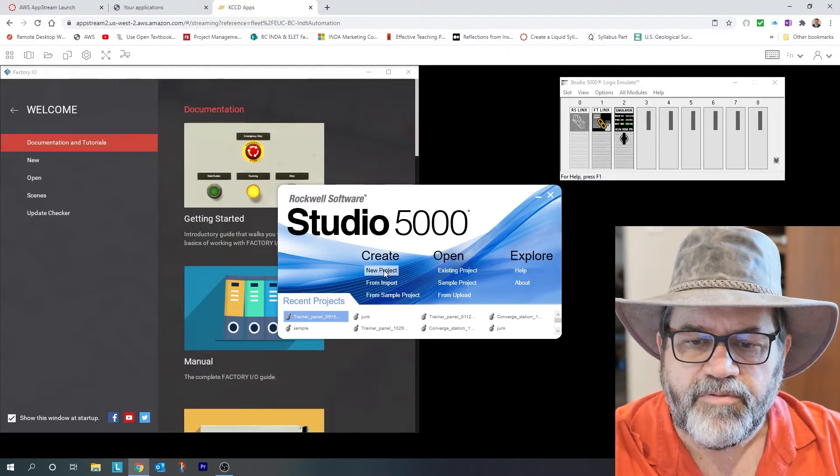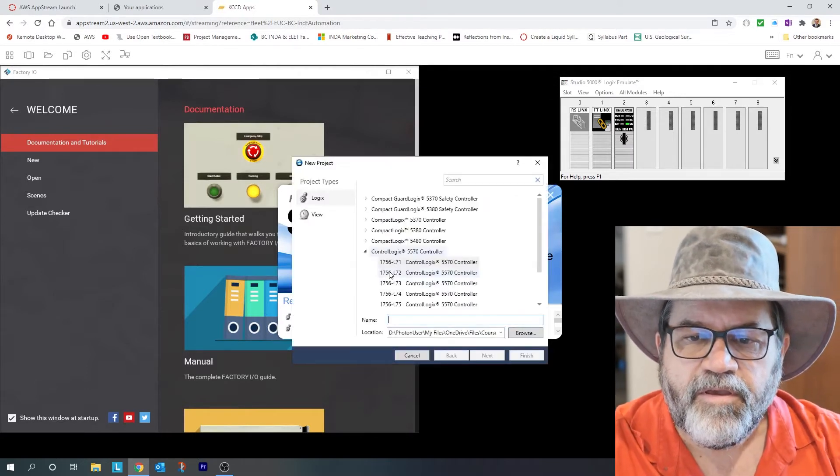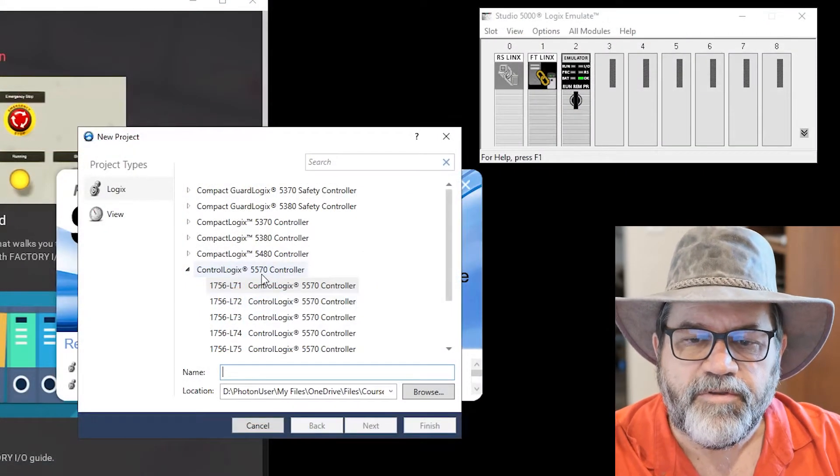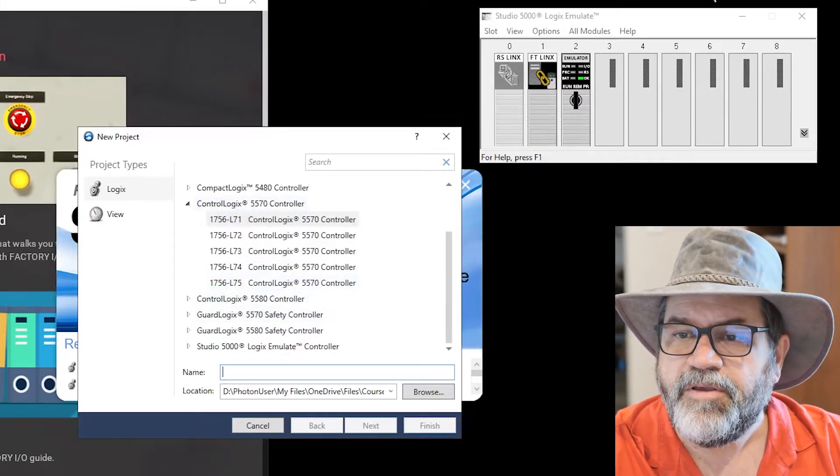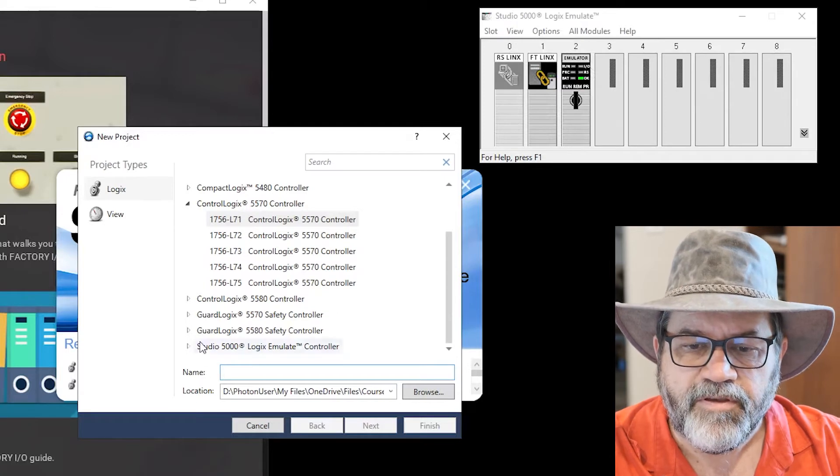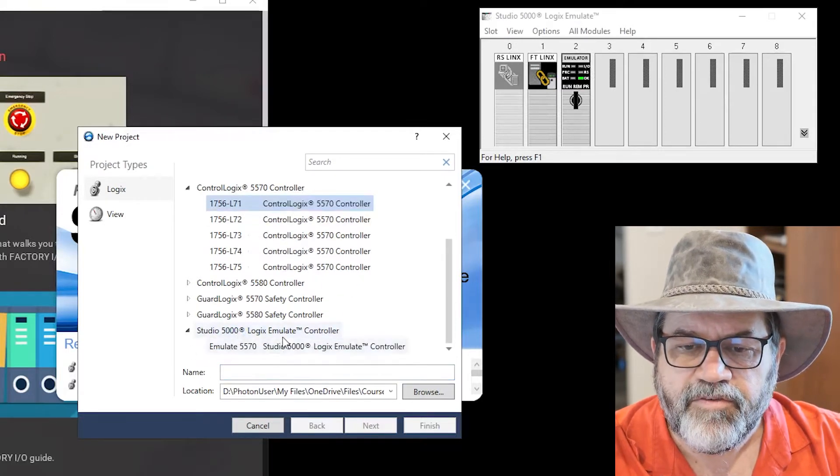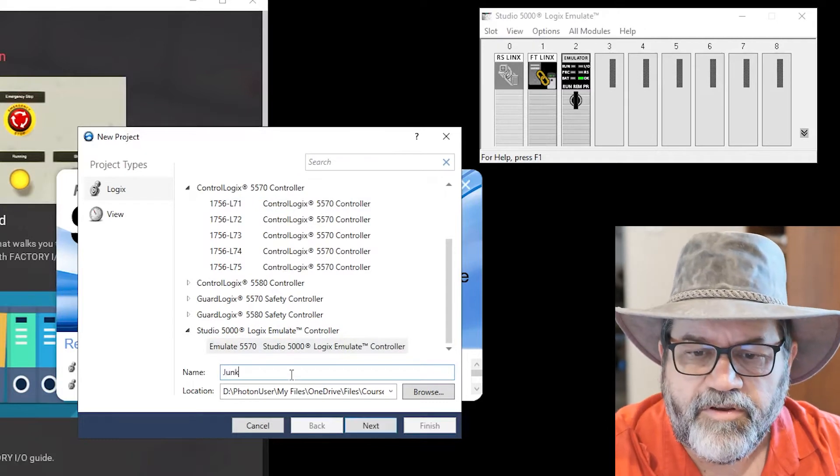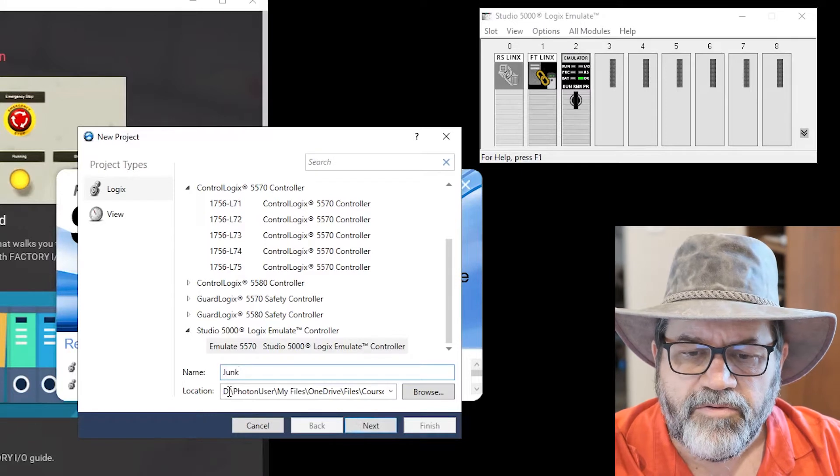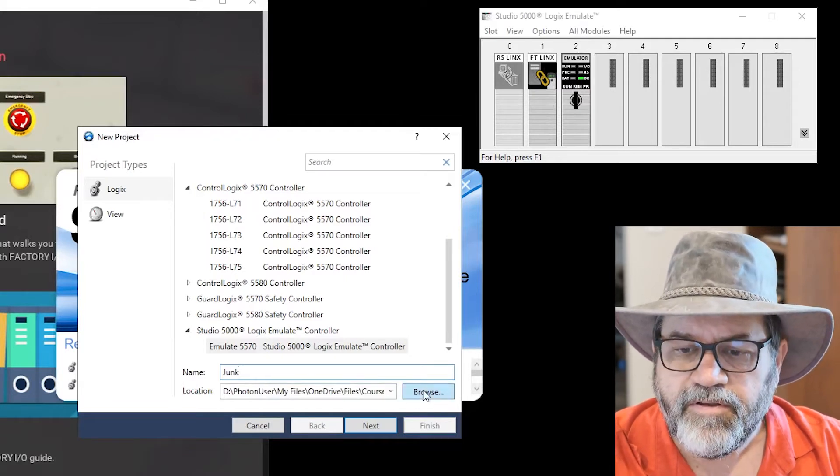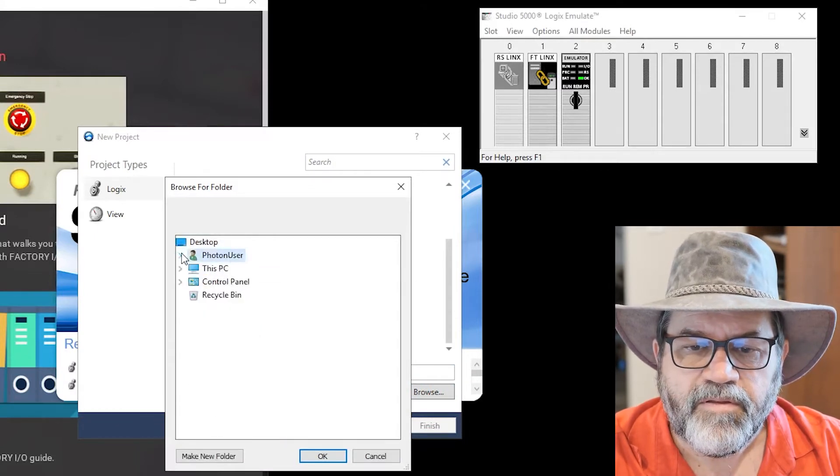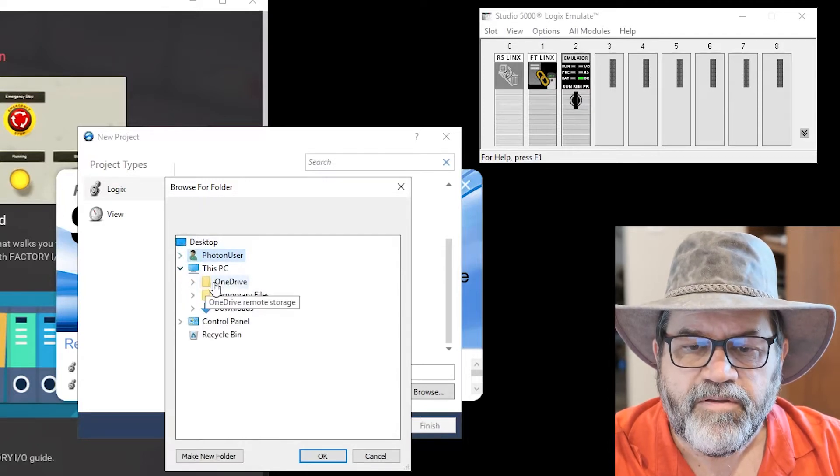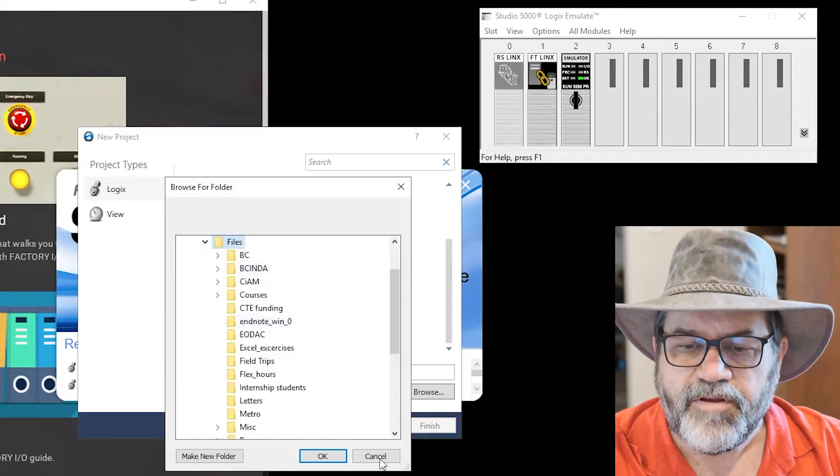I'm just going to open a new project, and when this comes up I need to change the controller type. The default is a 1756 and I need to use the virtual PLC. That's this guy here, and in slot two here is our controller in this virtual PLC. So I'm going to expand Studio 5000 Emulate and I'm going to select that controller. And for now I'm just going to call this junk because this is not a file I'm going to save. And location, well I don't want it saving on the D drive because that's a location I can't get to later on. So I'll click on browse, and on this PC there's my OneDrive and my files in my OneDrive. So I'm just going to save it there on my OneDrive.